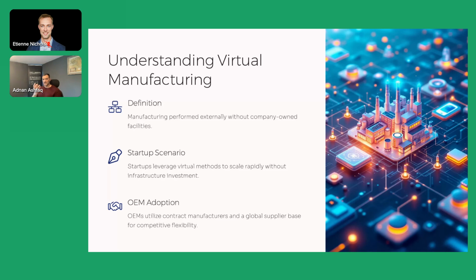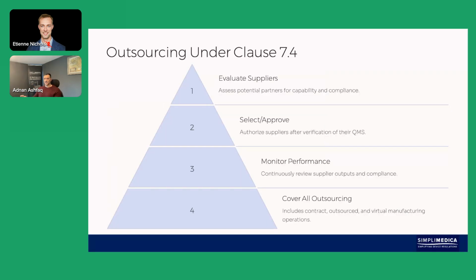When you're trying to understand virtual manufacturing, first of all, you need to understand the definition and your responsibility: you might still be the legal manufacturer, but you're outsourcing your manufacture to a vendor. That needs to be governed by clause 7.4 under supplier evaluation. Evaluate your suppliers, select and approve them. You might need to do an audit on them. So everything that we talked about earlier with regards to process validation, QC checks, and all the due diligence needs to happen to make sure that your outsourced manufacturer has covered all the areas.